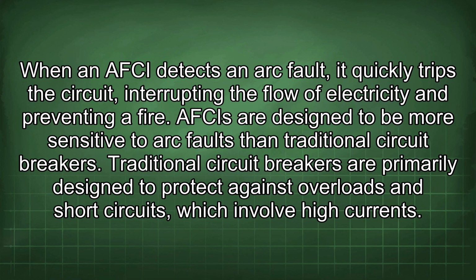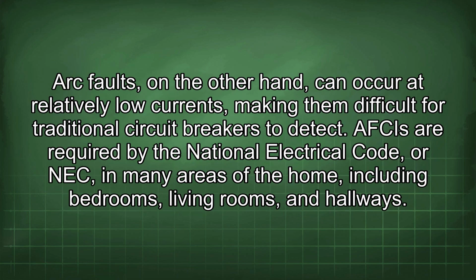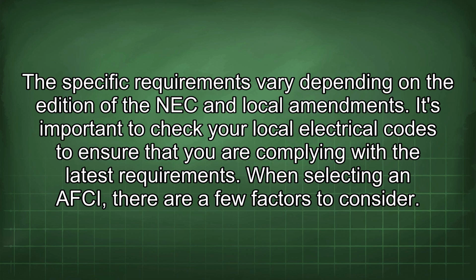AFCIs are designed to be more sensitive to arc faults than traditional circuit breakers. Traditional circuit breakers are primarily designed to protect against overloads and short circuits, which involve high currents. Arc faults, on the other hand, can occur at relatively low currents, making them difficult for traditional circuit breakers to detect. AFCIs are required by the National Electrical Code, or NEC, in many areas of the home, including bedrooms, living rooms, and hallways. The specific requirements vary depending on the edition of the NEC and local amendments. It's important to check your local electrical codes to ensure that you are complying with the latest requirements.